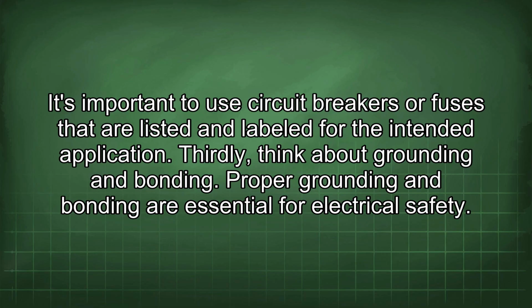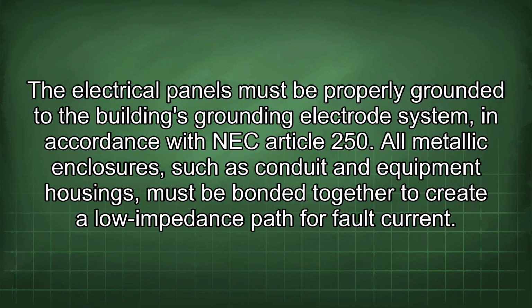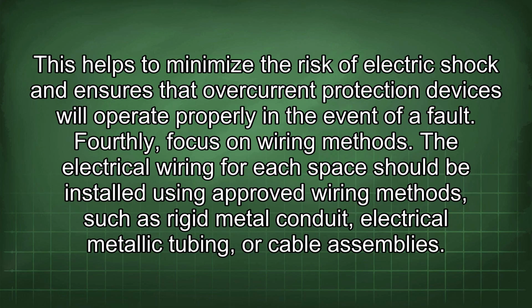Thirdly, think about grounding and bonding. Proper grounding and bonding are essential for electrical safety. The electrical panels must be properly grounded to the building's grounding electrode system, in accordance with NEC Article 250. All metallic enclosures, such as conduit and equipment housings, must be bonded together to create a low impedance path for fault current. This helps to minimize the risk of electric shock and ensures that overcurrent protection devices will operate properly in the event of a fault.